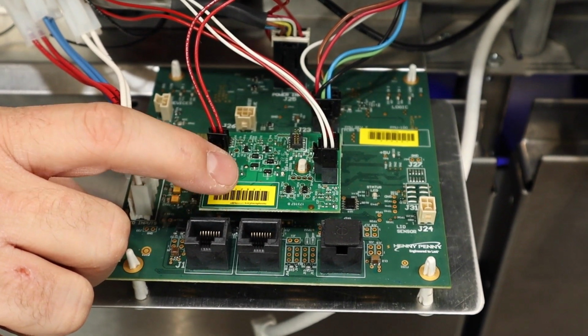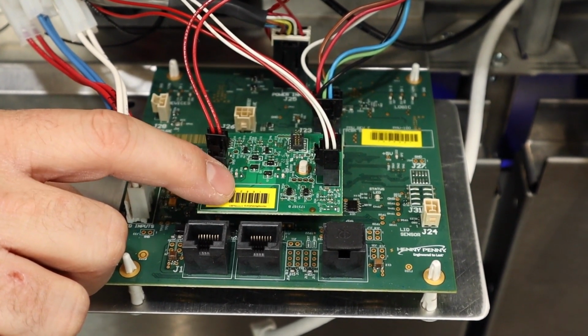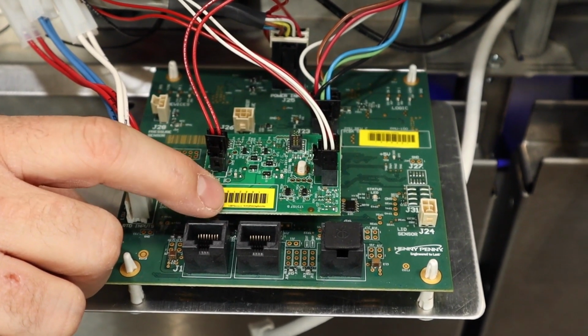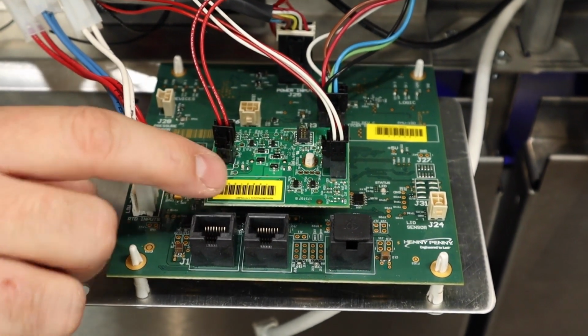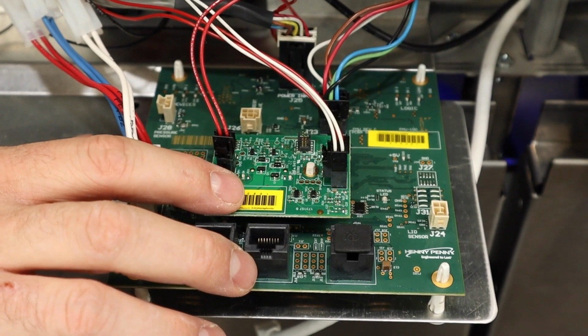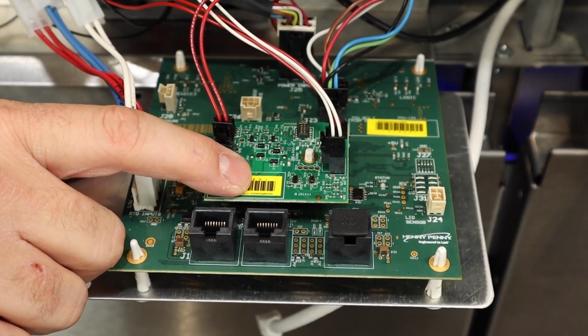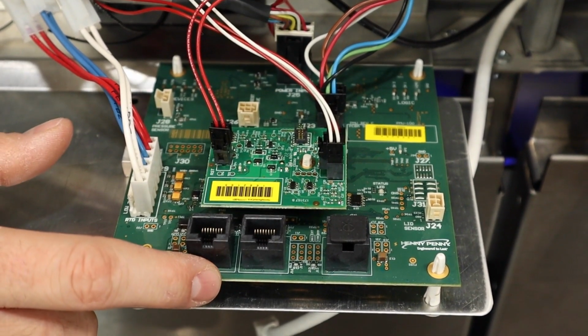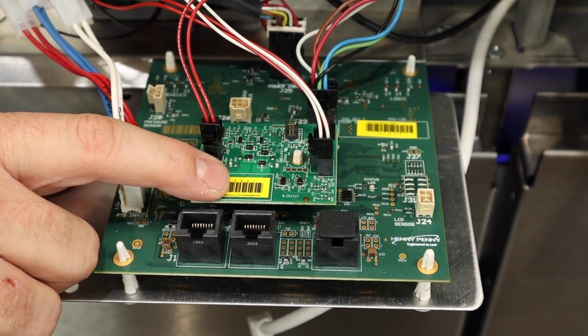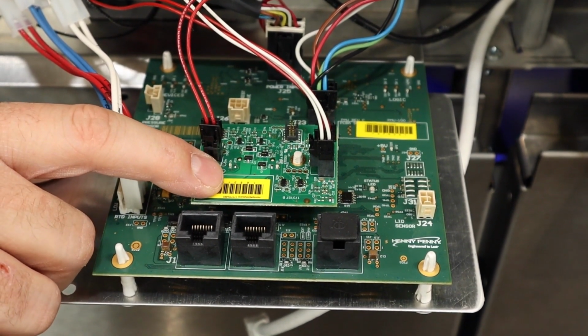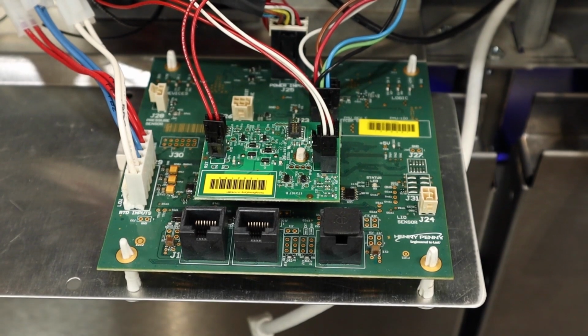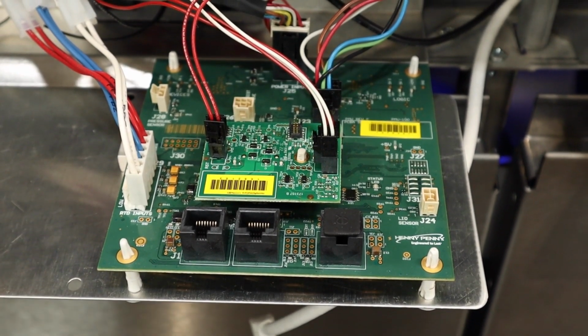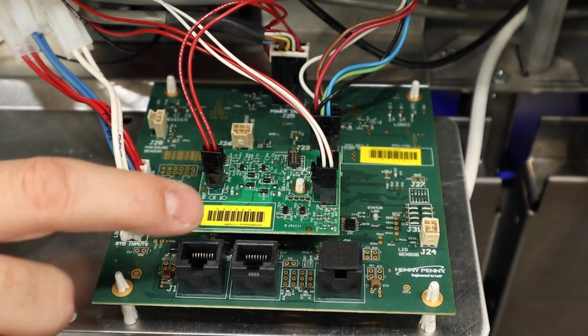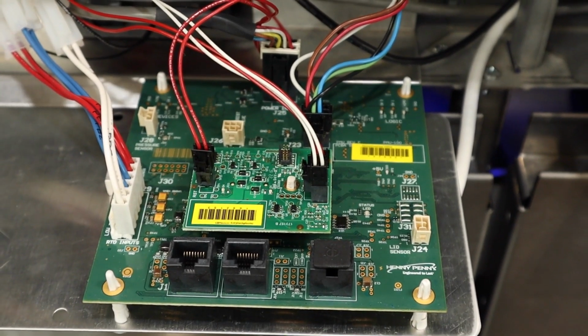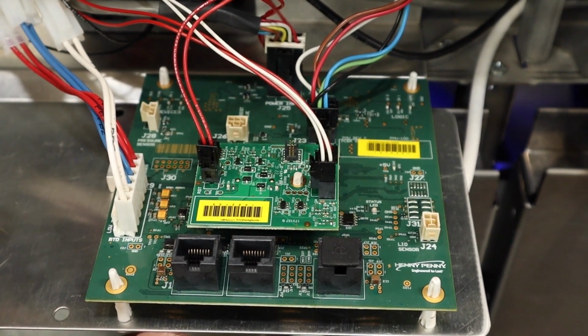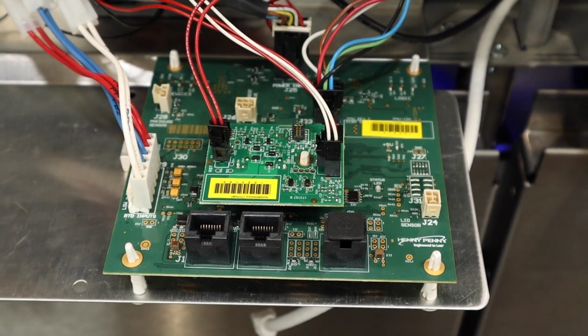So we could do the same troubleshooting for that E-10V as in voltage error code as what we did for the E-10W, and basically power the unit completely down for safety, unplug this high limit PCB from the PMU board, and then reconnect it to see if it was maybe just a connection issue, turn the unit back on and see if that takes care of it. If it does, great. However, if it didn't take care of it, then it's most likely going to wind up being our high limit PCB board, or last but not least, potentially the PMU board.